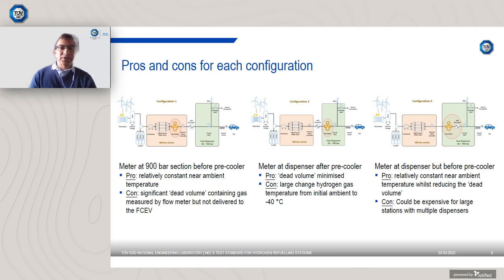To counteract this issue of dead volume, what some refueling stations have done is install the flow meter at the dispenser unit. However, in this case, because it is installed downstream of the heat exchanger, the flow meter would initially be at ambient temperature and then suddenly start seeing gas coming in at minus 40 degrees C. And this varying temperature that the flow meter sees would affect the accuracy of the flow meter measurements.